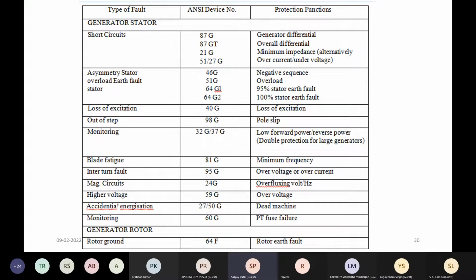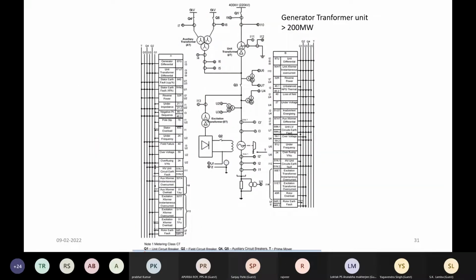Various protections are against each hazard. The protections are listed here. You have to remember the different types of generator layout. This is one of the commonest layouts of the generator. There is a generator, there is an auxiliary transformer for excitation, and then there is a station supply transformer, auxiliary UAT, and then there is a generator transformer connected to the grid. So all these protection schemes, we have to see that they maintain their integrity and no malfunction takes place during the grid disturbance.